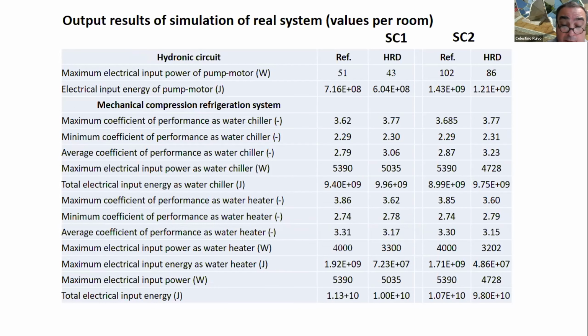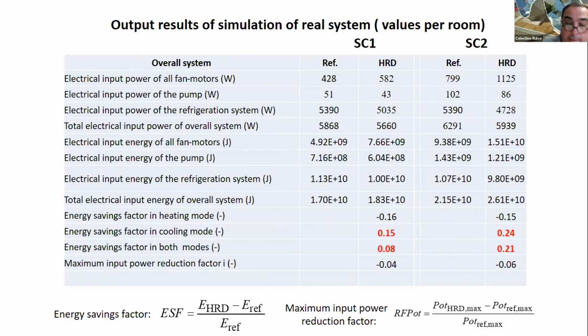Regarding the machine used for cooling water and for heating water, its maximum electrical input power and its electrical energy consumption are smaller when adopting a heat recover device. In spite of the mentioned positive impacts, the higher electrical energy consumption associated with the operation of the two fans of the dedicated outdoor air system has a negative impact on energy savings when the heat recover device is used.